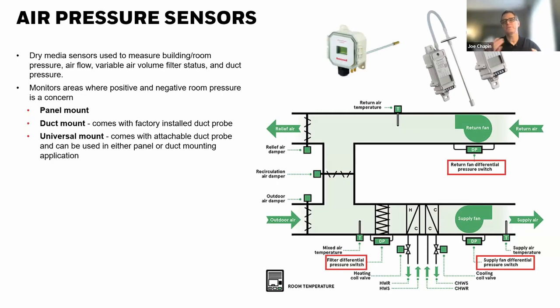So I would install negative pressurization systems in sick rooms, maybe wood and metal shop, auto shops where there would be fumes, maybe some art rooms where they may be using paint, things of that nature. So again, negative pressurization, you see more of that than positive in a lot of cases. You'll see positive pressurization in data centers, but the point is, if I put these air pressure sensors in place, I can control the pressure and control the airflow of a room that best suits my needs. So again, air pressure sensors are another connected option that you can do with your facility itself.